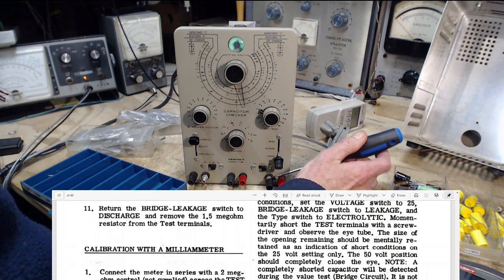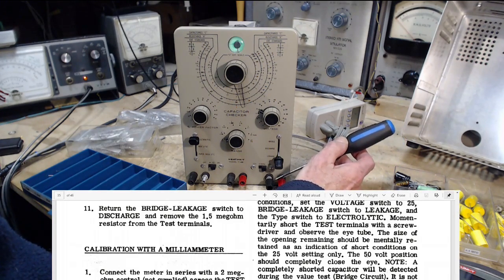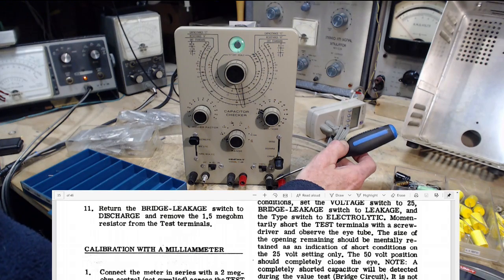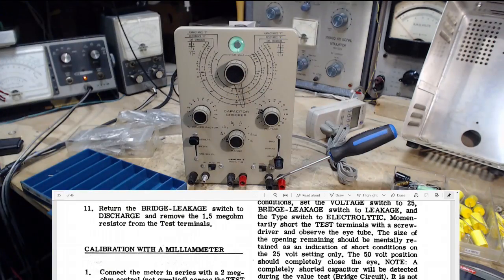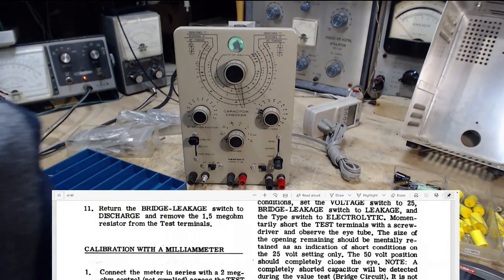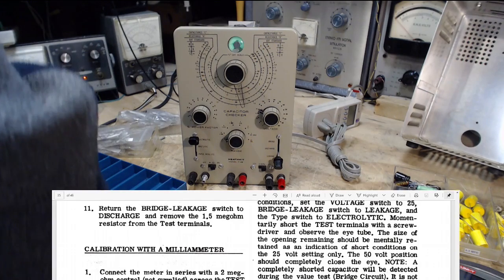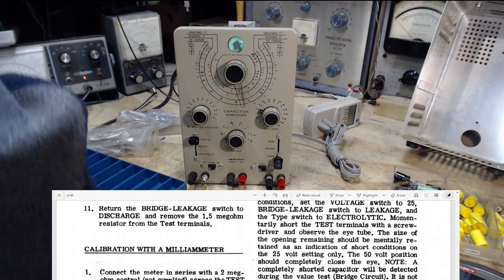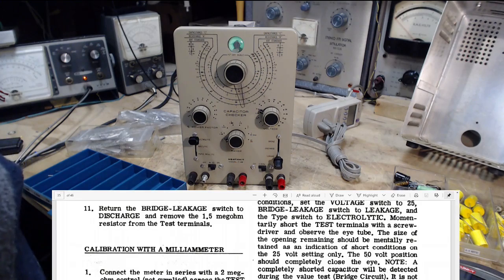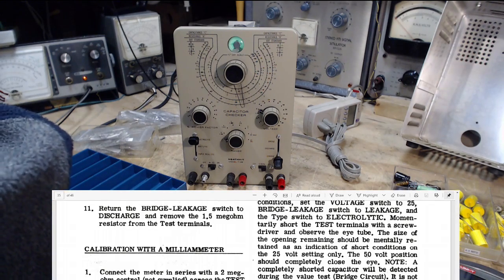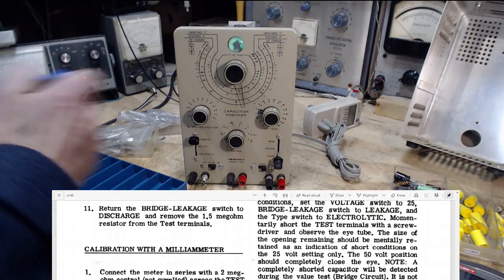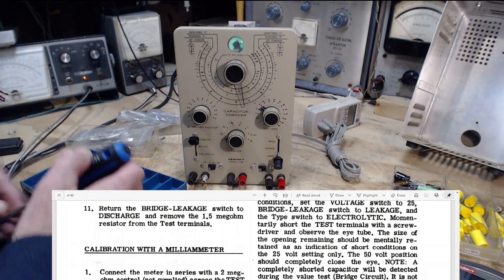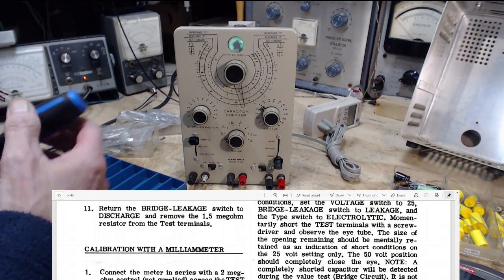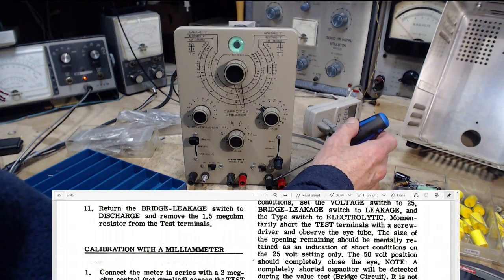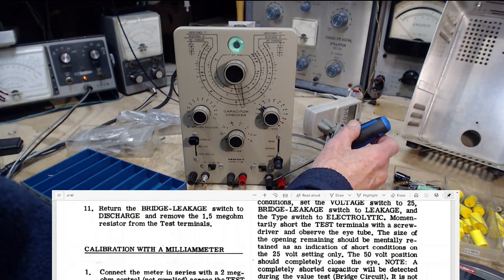So what they're saying is if you put a shorted capacitor in here, that's what you'll see at 25 volts - almost closed all the way. This is just momentarily. The size of the opening remaining should be mentally retained as an indication of short conditions on the 25 volt setting only. The 50 volt position should completely close the eye. Yeah.